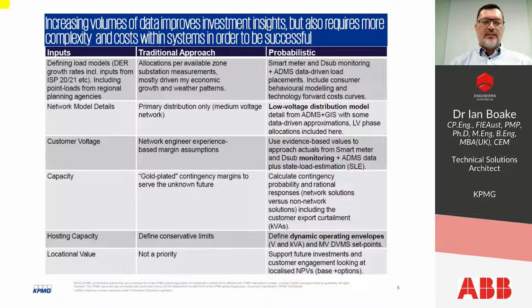Voltage, as I mentioned, is a key parameter to be managed within the network, especially at the end of the network. And in some instances, you don't need complete metering of the whole network. You can use something called state load estimation, which is really filling in the blanks using Kirchhoff's current and voltage laws to give you the necessary visibility. But it does require a certain minimum amount of metering or measurement on the network. There's always been this issue in terms of capacity gold plating. And so prudency and efficiency is very, very important in terms of investing where the problems are and enabling the right amount of DER without curtailment, preferably.